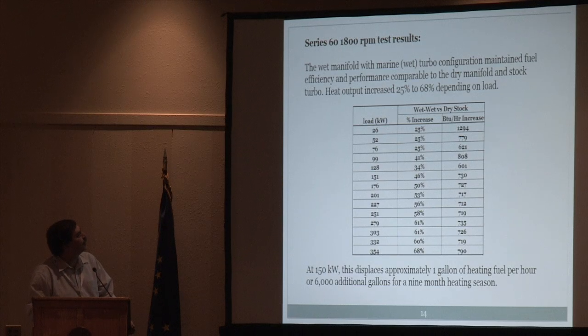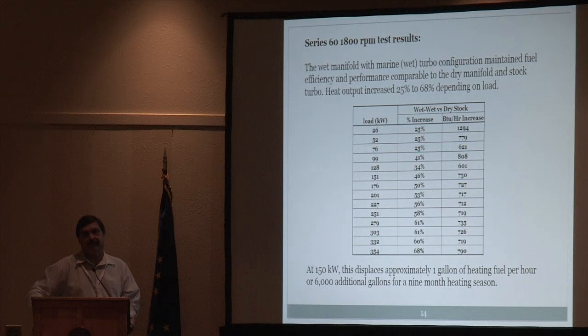The results of the 1800 RPM test proved out that the wet manifold with the marine wet turbo configuration maintained fuel efficiency and performance comparable to the dry manifold and stock turbo. With varying load came varying heat output, anywhere from 25 to 68% more heat. If you figure your average load is 150 kW, this displaces almost another gallon of heating fuel per hour during the winter months, or could add up to 6,000 additional gallons during a 9-month season. That can be pretty significant if you're paying $5 or $6 a gallon for fuel.